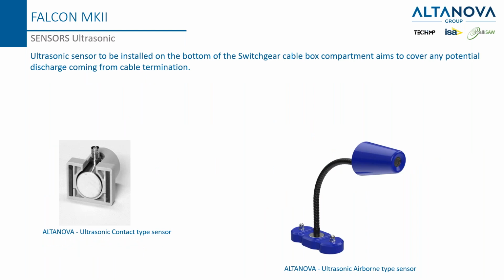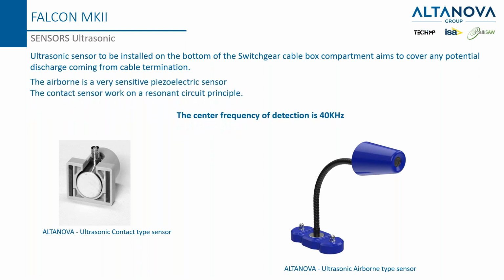About the ultrasonic sensors, Altanova can provide two different types of ultrasonic sensors, and basically they are installed on the bottom of the switchgear cable box compartment, aiming to cover any potential discharge coming from the cable termination. The airborne is a very sensitive piezoelectric sensor, and the contact sensor works on a resonant circuit principle. Both of these two sensors have a center frequency of 40 kHz.